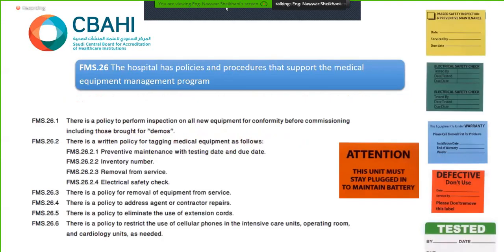There should be a policy to perform inspection on all new equipment before commissioning, including equipment brought in temporarily — this is a dedicated policy. We should also have a written policy for tagging, which may differ between four to seven tags. It's unlimited and based on hospital policy, such as PPM, inventory number, serial number, removal from service, and electrical safety check.